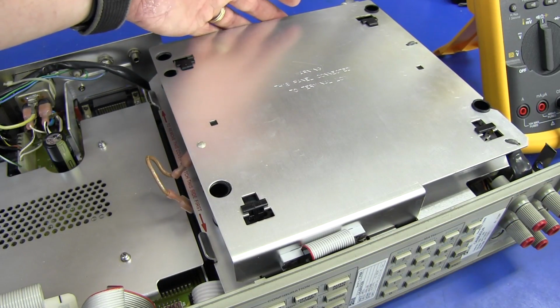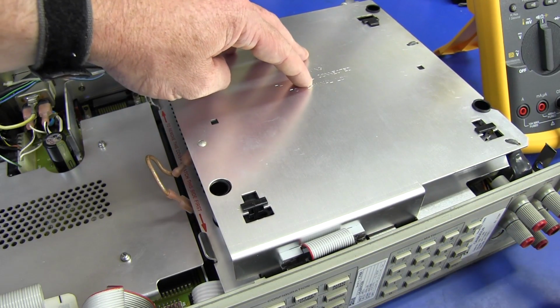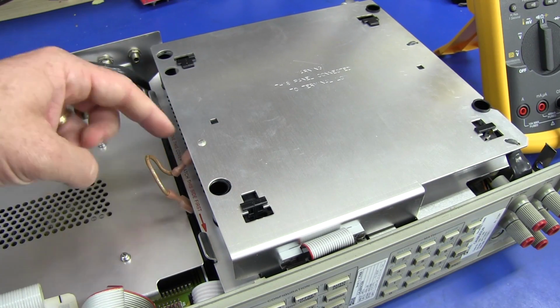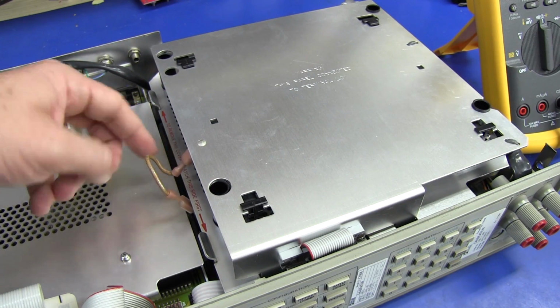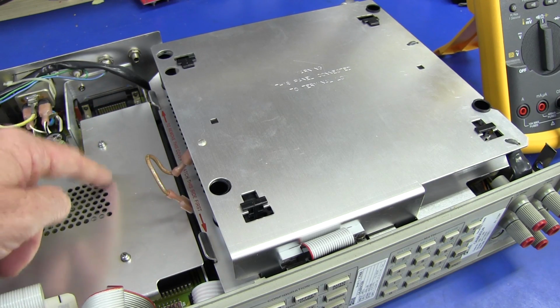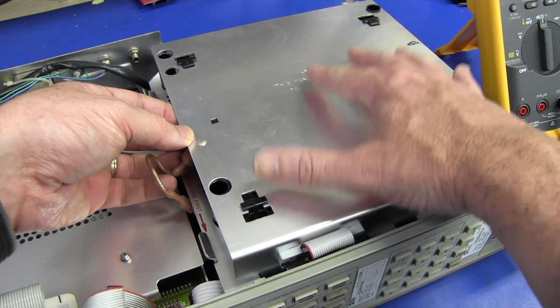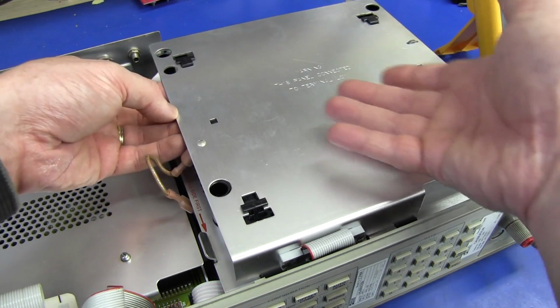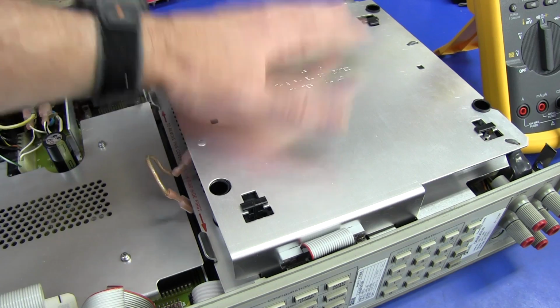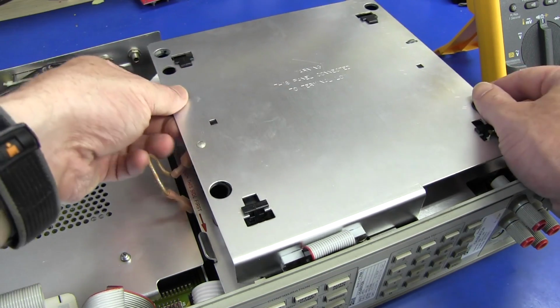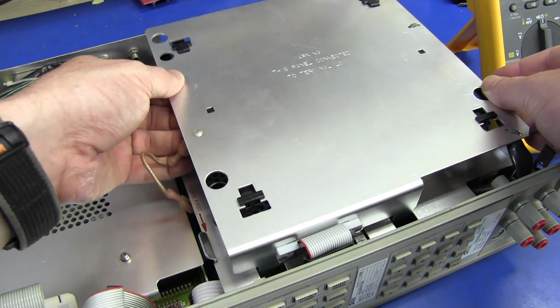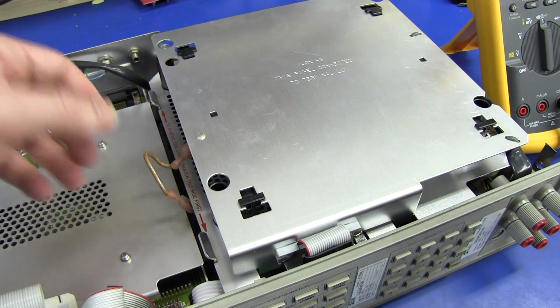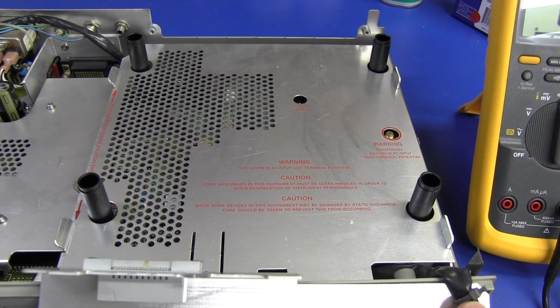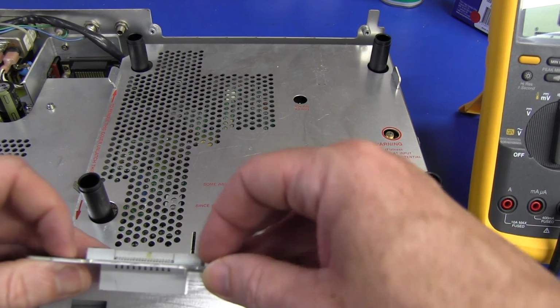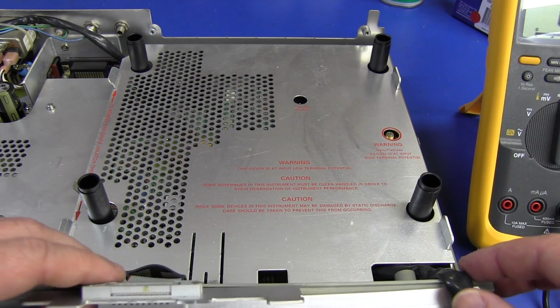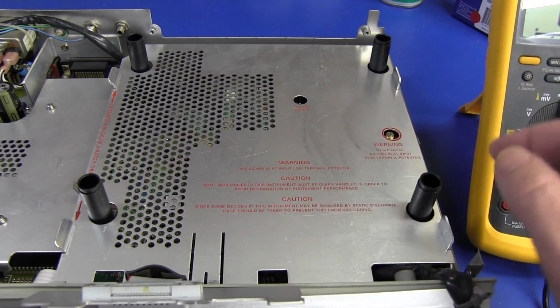So this grounded top cover here, and when I say grounded, I actually mean ground and not mains earth, as we just saw. It's connected through to the bottom cover down here, which is also separated from mains earth over here. So that one is just the shielding cover for the relay input switching matrix board, which then slots in underneath here. So we should be able to lift that out, and somehow it's got instructions there, should read it. And if we just flip that cover open, it's held on there via this ribbon cable that's attached, and I won't disconnect that unless I absolutely have to. But you know, warning, caution, caution.